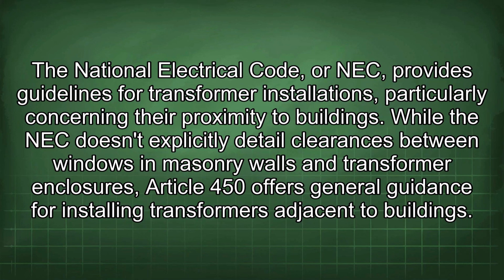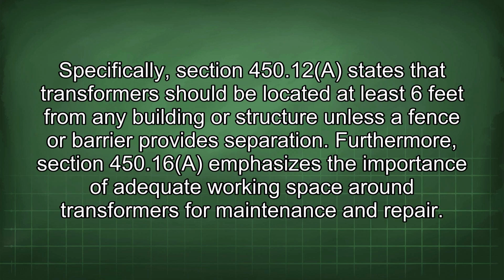The National Electrical Code, or NEC, provides guidelines for transformer installations, particularly concerning their proximity to buildings. While the NEC doesn't explicitly detail clearances between windows in masonry walls and transformer enclosures, Article 450 offers general guidance for installing transformers adjacent to buildings. Specifically, Section 450.12 states that transformers should be located at least 6 feet from any building or structure unless a fence or barrier provides separation.